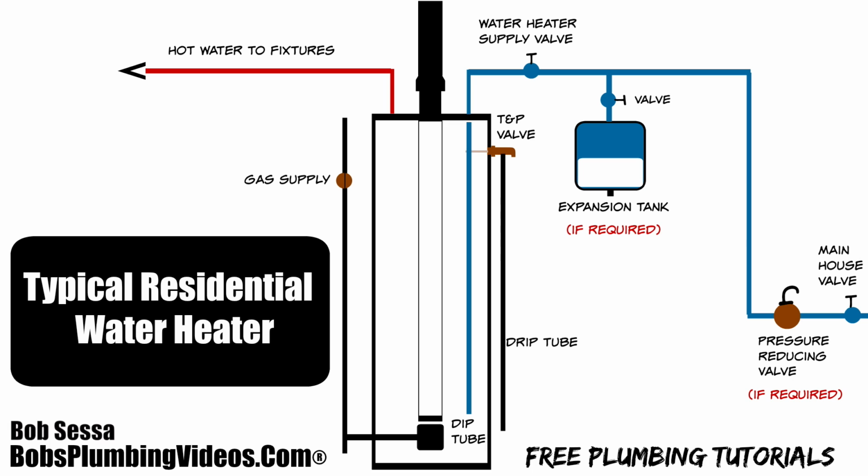So another reason that T&P valve may drip is they're spring loaded. They have a washer in them. They have a little seat in them, as in a faucet. Sometimes if they start to relieve and there's some dirt trying to get out of there and the dirt gets caught between the washer and the seat, it'll continue to dribble. I'm not talking about just all out relieve. It'll just dribble on the floor and you can't get it to stop. And some manufacturers say that once a relief valve has relieved itself, it's time to change it. It's very hard to get it to stop. You can flip that little silver lever on the end of it in an attempt to wash the dirt out of there. But in a lot of cases, I've actually gone in and just changed the valve.